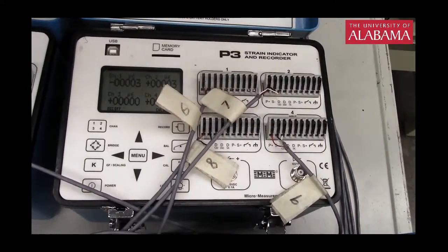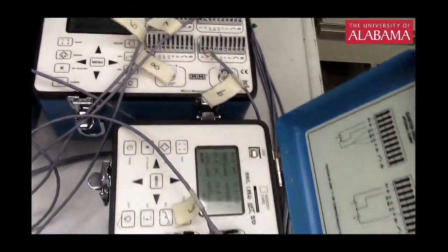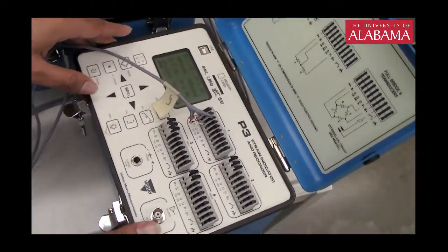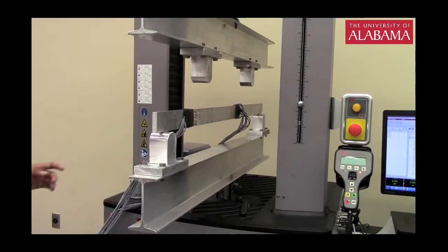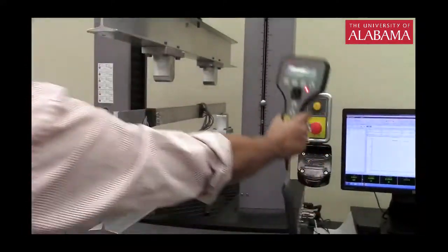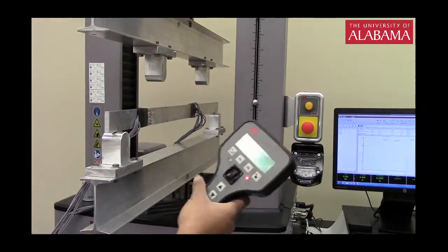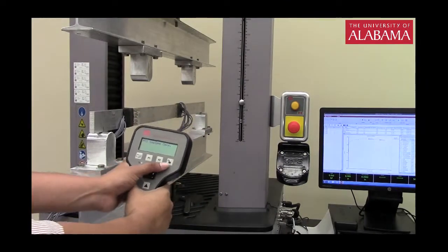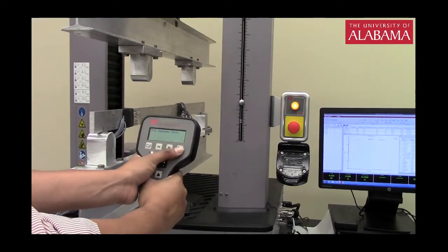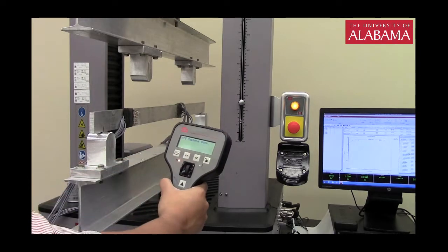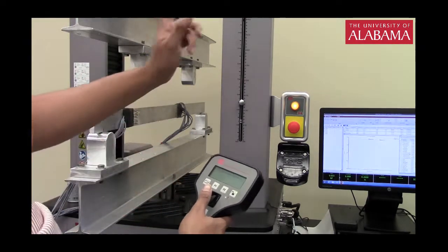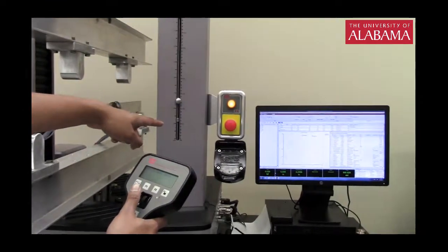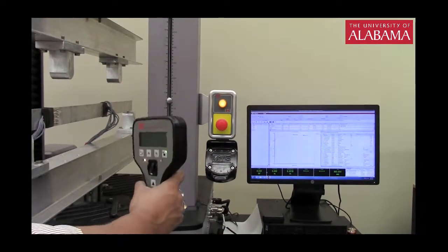Now coming back to the fact that we did not attach the 5th gauge. So actually my 5th gauge is attached to this particular remote. Let me go ahead and take the handheld remote so that I will be able to control the load quickly. So I'm just going to press this key, which is green, which when it turns green, that means my remote is active. So now if you see the load on the computer, it reads 0.